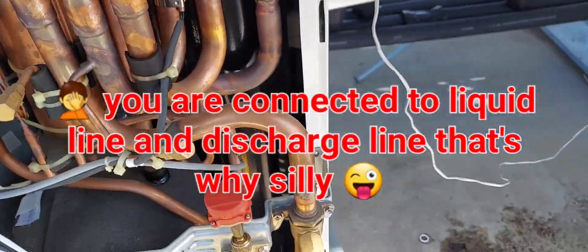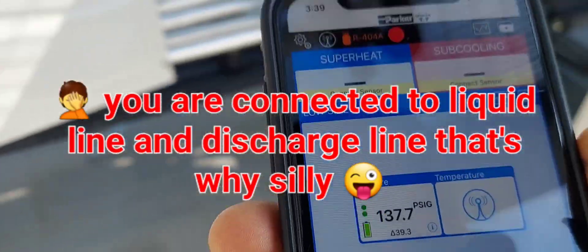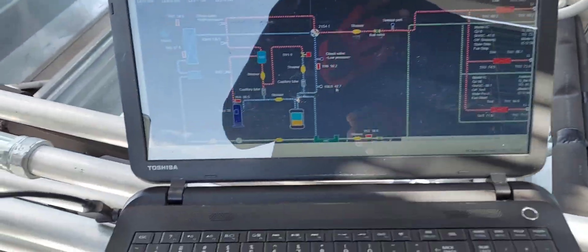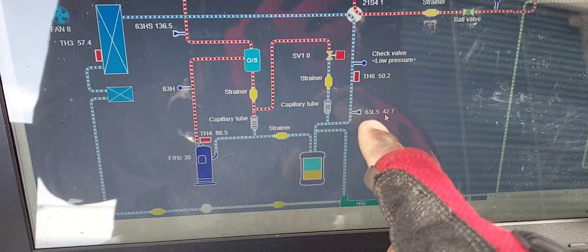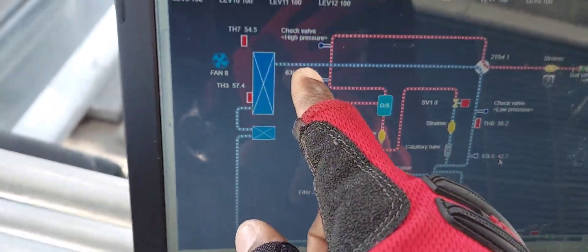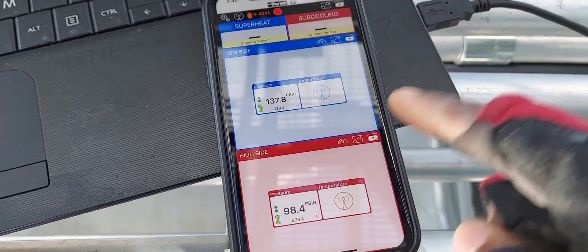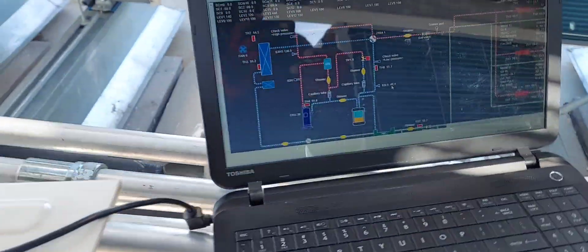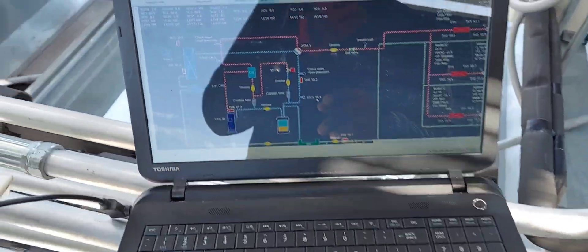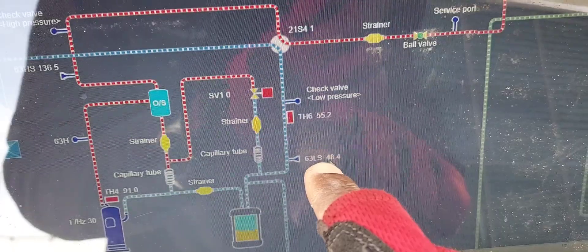The pressures are different from where my sensors are connected — I'm reading 98. I'm reading 42 and 135 on my sensors. My sensor is probably picking up a different point outside. But those error codes — that's what they mean: these are diagnostics with low refrigerant.